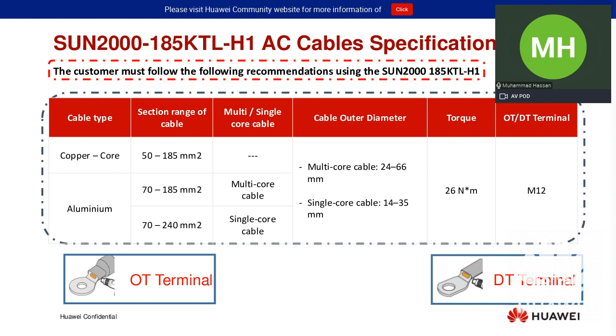Three weeks back, there was a site here in the UK. The customer didn't do the proper torquing or crimping of the AC connector, so there was a problem, and we went to that site. We investigated everything, and in the end, we found out that the torque settings were not applied correctly on those inverters. That's why they were facing heating issues with that inverter.